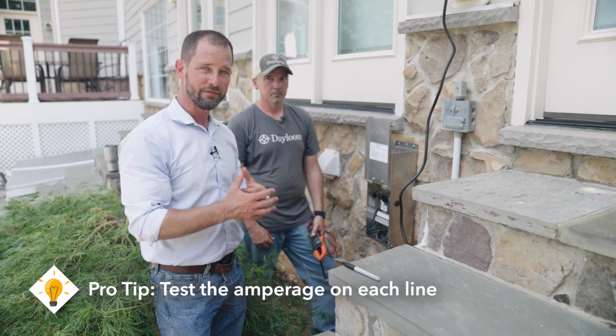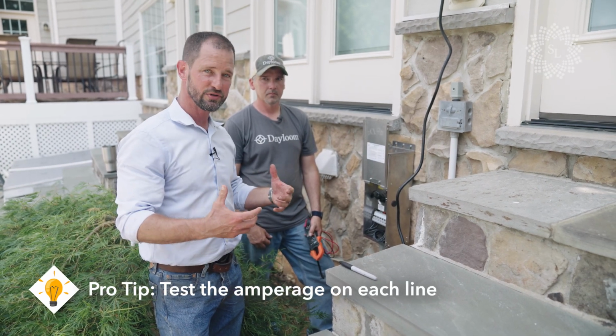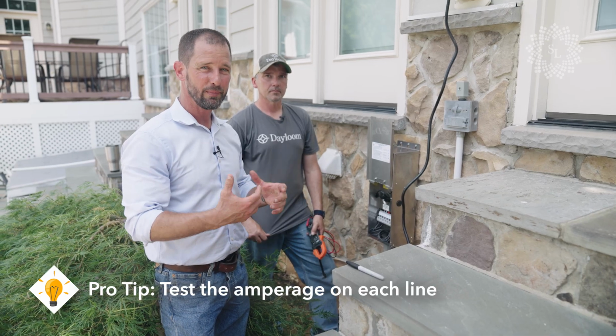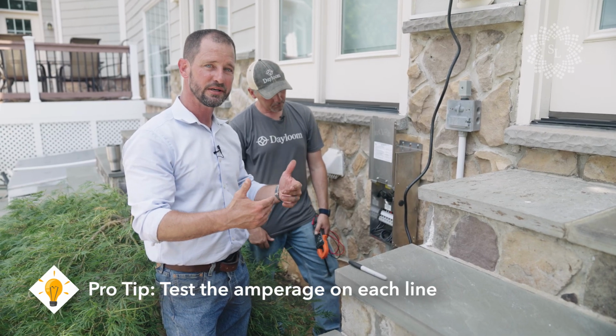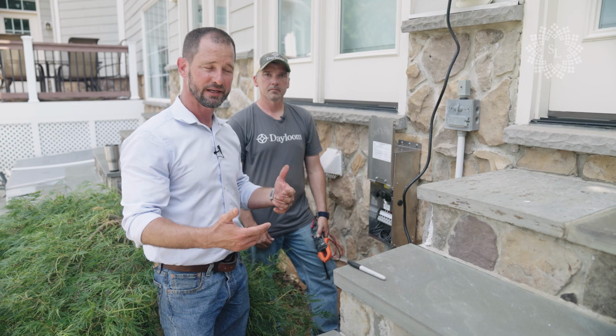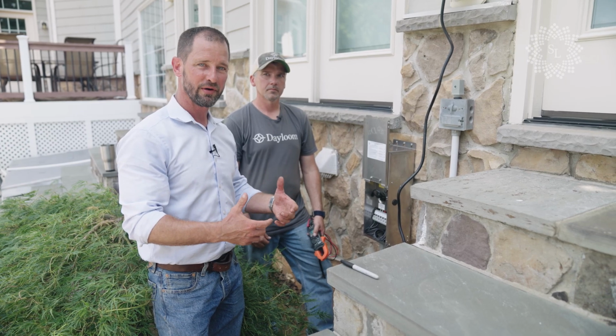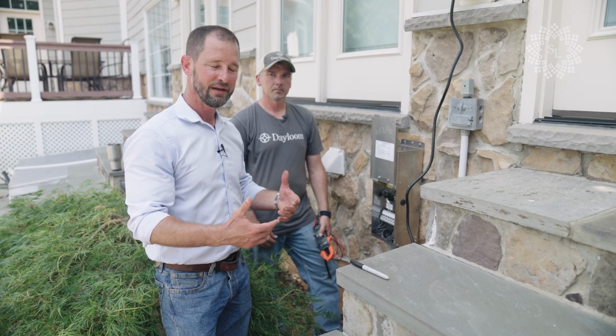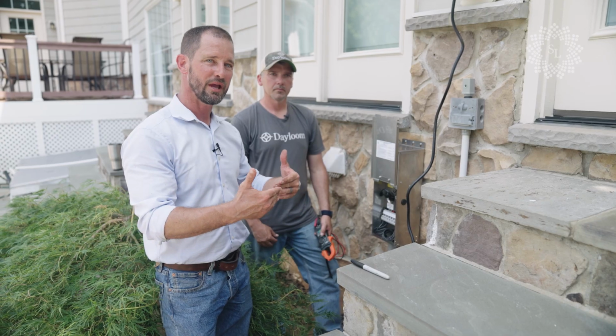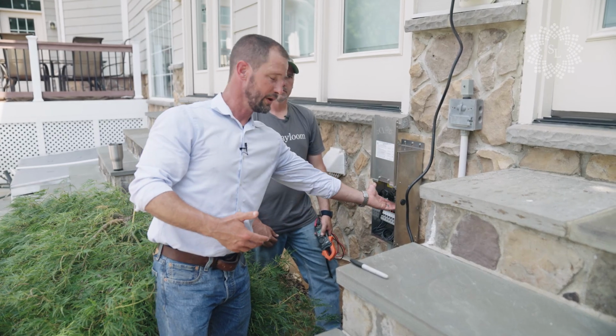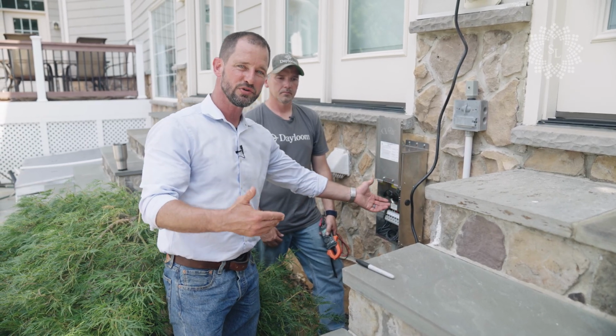So we're at final verification on everything, testing on the transformer. We're looking at amperage—amperage is really important, it's what shows us how much energy is on each line. Very often people don't mark the amperage and don't track it, and you could find yourself where the overall amperage on one of the secondary circuits is like 22, 23.